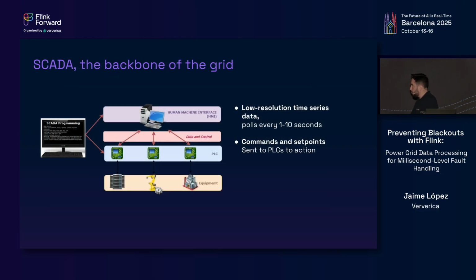And how do we make sure that we don't have problems on our hands? The backbone of the grid is controlled and monitored by SCADAs. I think it was something like supervisory control and data acquisition systems. They're relatively old-fashioned, very robust systems that were put in the grid when these dispatchable plants were built. They're really good at most things. They are the ones that issue commands to PLCs that are going to action a switch, a voltage regulator, that can actually take physical actions.